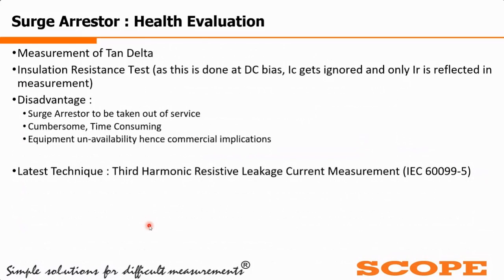Now when we are doing the insulation resistance test, we are doing this test with a DC bias. So IC gets ignored because capacitance will not come into the picture, and only pure IR is getting reflected during the measurement. But the disadvantage of these two measurements, tan delta and insulation resistance, is that the surge arrestor needs to be taken out of service. So it is cumbersome and time consuming, because for only LA testing, getting the line shut down is a very tough job in today's scenario, and the equipment or the line will be unavailable during this time. So there will be commercial implications.